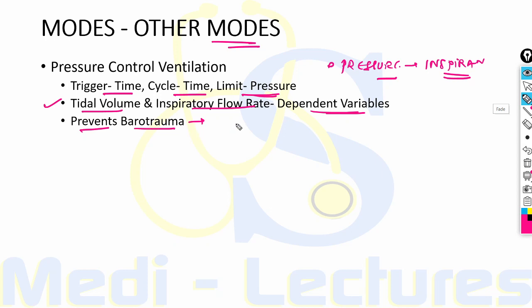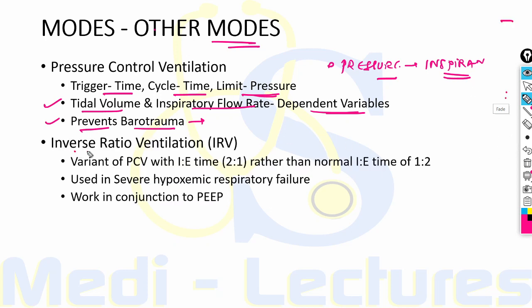Inverse ratio ventilation is a variant of pressure control ventilation in which the inspiratory-to-expiratory ratio is prolonged to 2:1 rather than the normal 1:2. Due to this longer inspiratory phase, it is used in patients with severe hypoxemic respiratory failure. It increases distending pressure without increasing peak airway pressure.